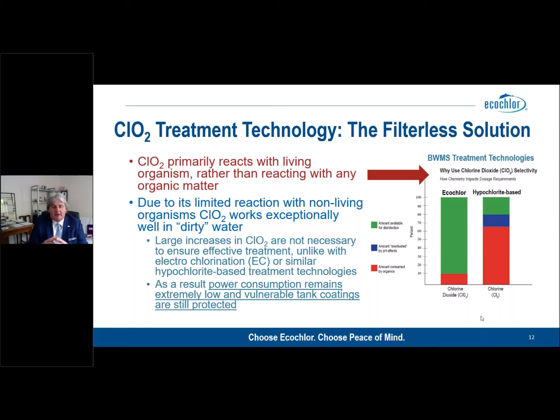Now, all right, we know that we have to increase a hypochlorite dose, but the problem with that is that more dose means more electrical power consumption, and an extremely high dose represents a potential danger for tank coatings, which are quite vulnerable in these circumstances. So high levels of hypochlorite in the tanks is a bad thing for the longevity of the tank coatings and thereby the structure of the vessel underneath.